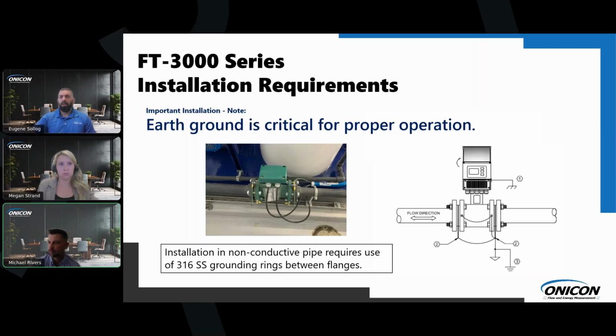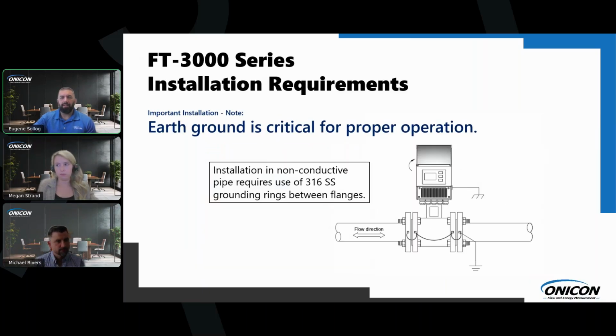Good question. We have these everywhere in our manual. So I just took a snip out of the manual, and we have this all over the place for grounding in non-conductive pipe. But yes, you're correct. This says non-conductive pipe here, but there's still grounding required on this, just bonding two flanges together.